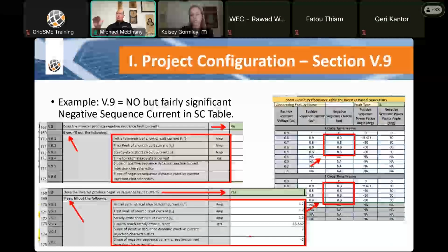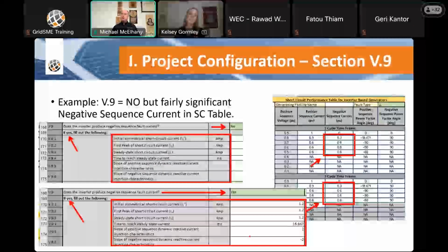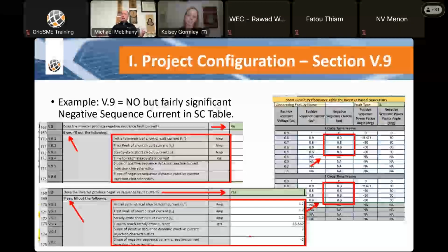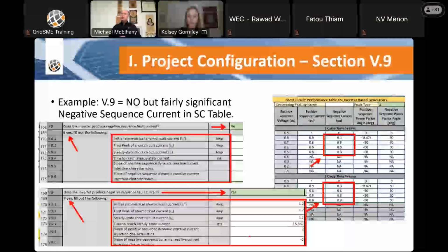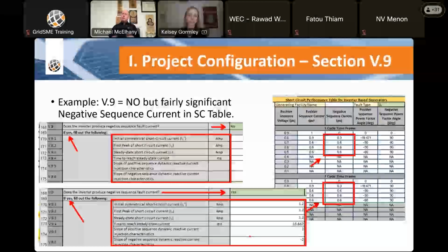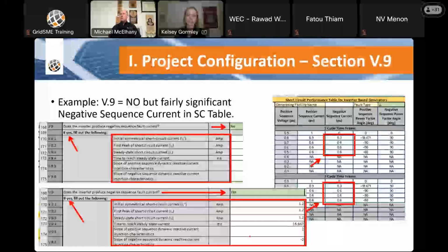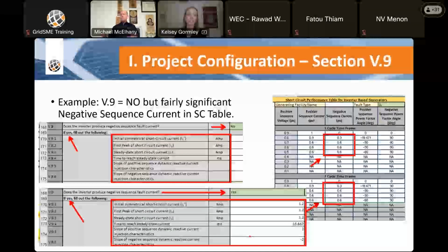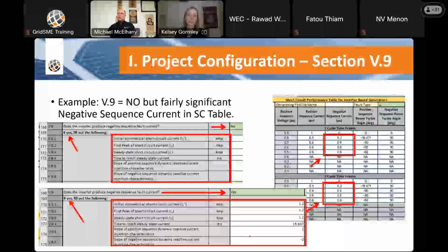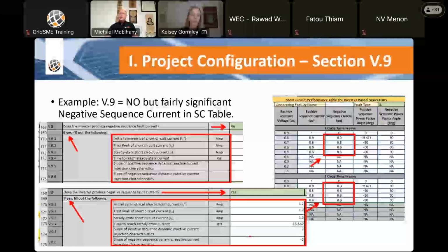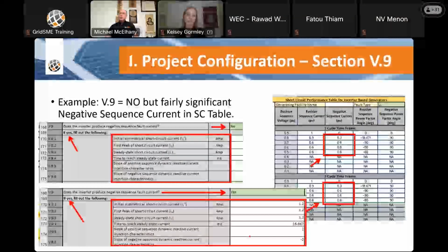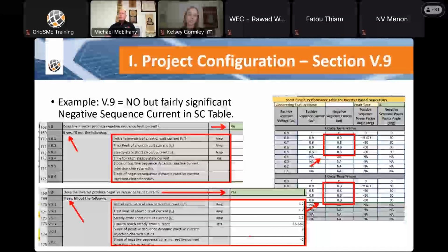Yeah, this is a lab that said it had this, but under a normal condition, we're still saying no. SMA says, well, you can't answer the question yes and no, so let's say no for balanced three-phase faults and see what CAISO says. So far, they've allowed that. And then there's the issue that in some cases, PG&E is starting to require that inverters that can enable negative sequence fault current do so when you're interconnecting with them as the PTO.